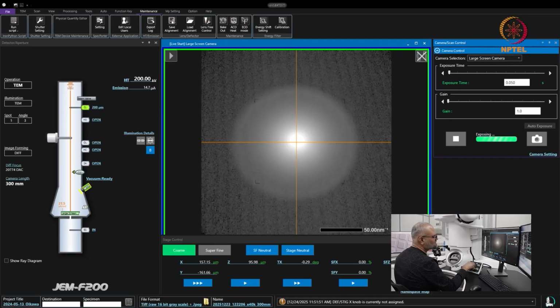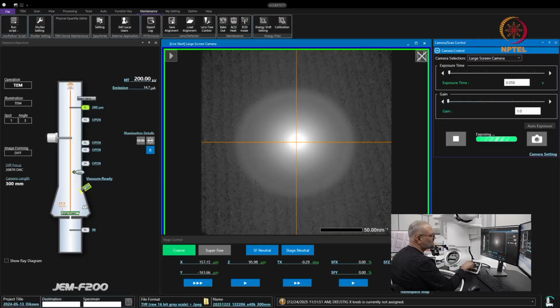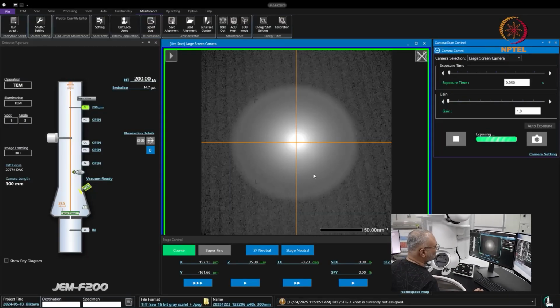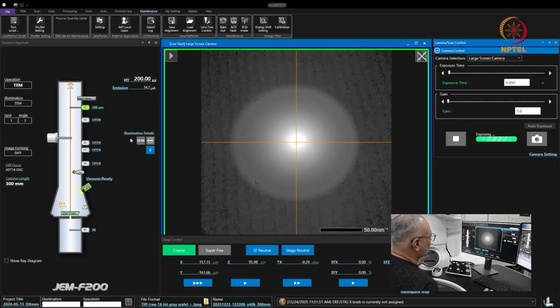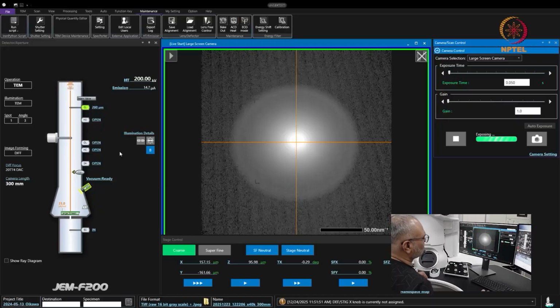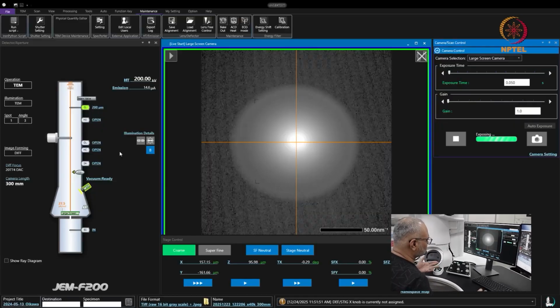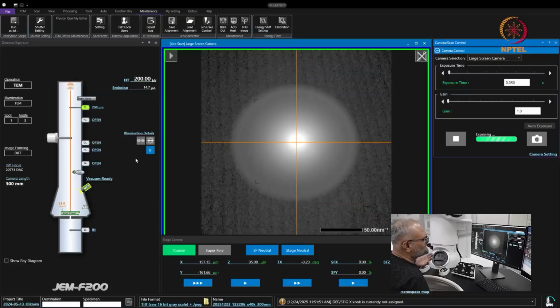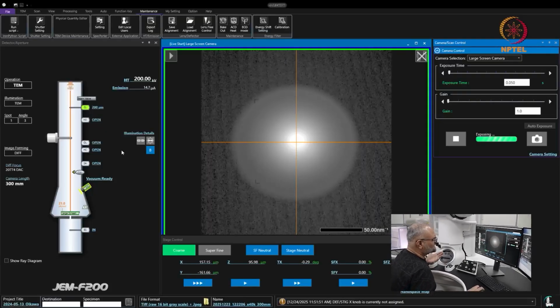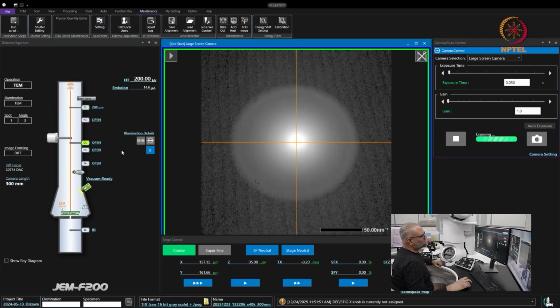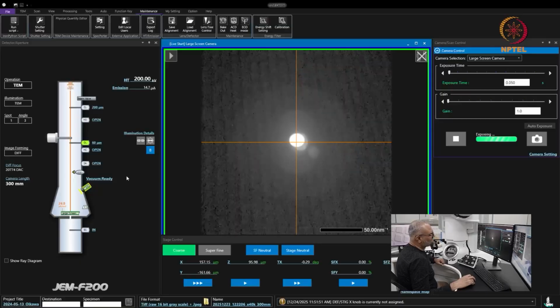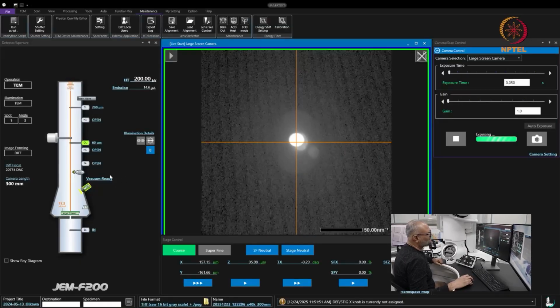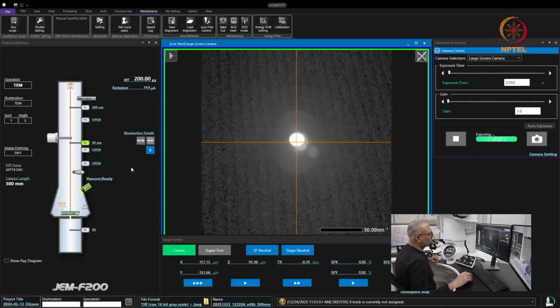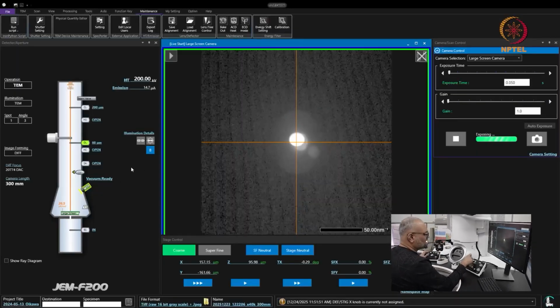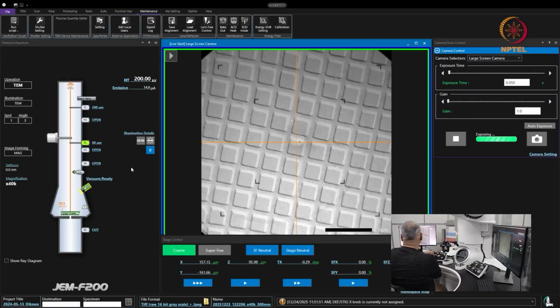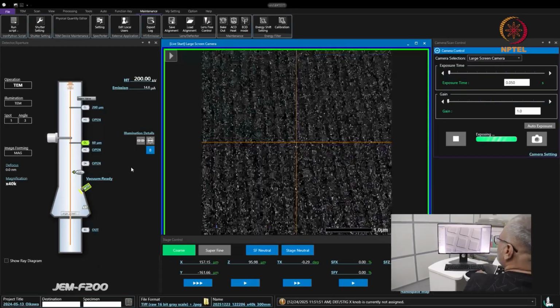As you can see, at one point you see the rings. I'm not looking in particular for any specific kind of an image, but just to enhance the contrast, so I can put in one of the objective apertures of 60 micron in. So when I click this diffraction button, what I'm seeing here is already the back focal plane of the objective lens, which is where your objective aperture is lying. And when I click insert, the aperture goes into the plane. The aperture is more or less centered with the center of the diffraction pattern or the brightest spot, and I go back to image mode again by pressing mag, and let us see how the difference in the image is when I put in the aperture.